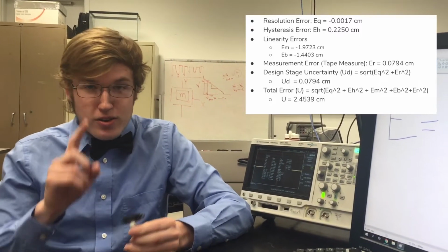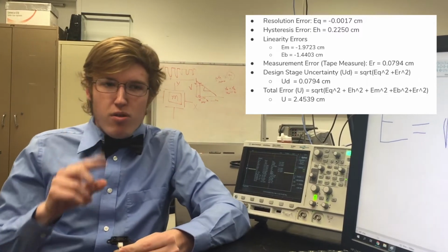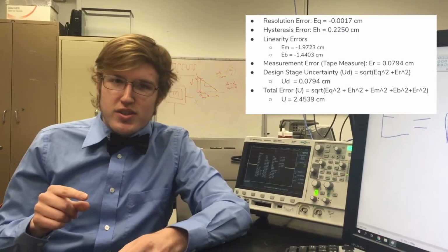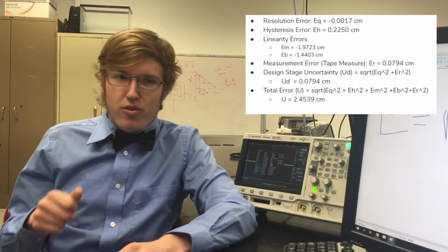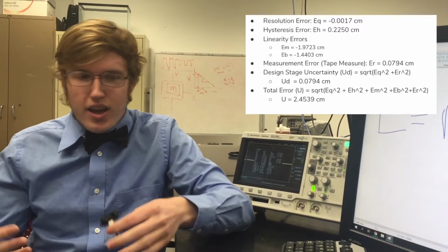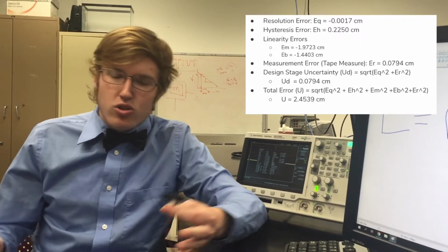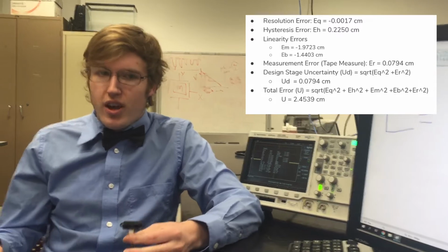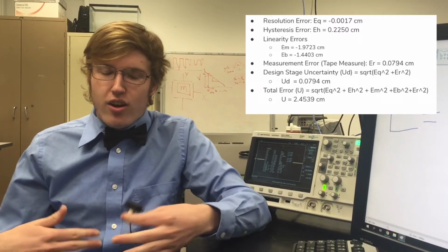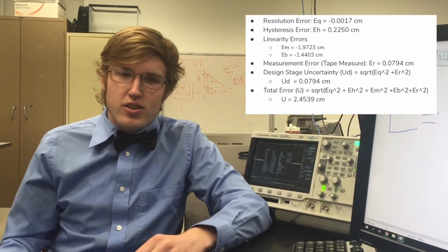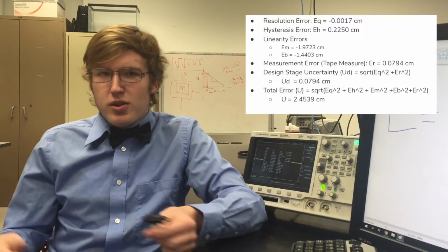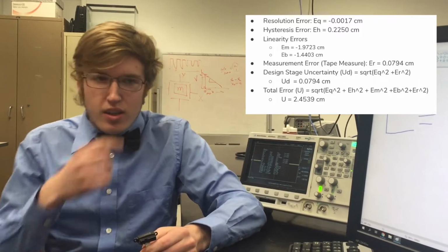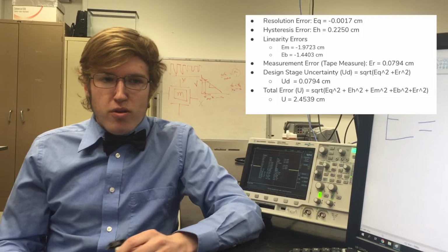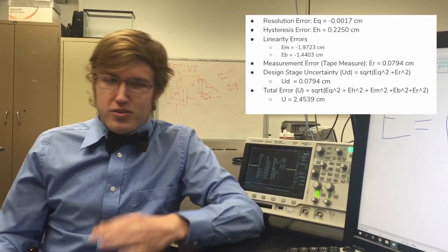Now our linearity errors, those were the biggies. We had negative 1.9723 centimeters and negative 1.4403 centimeters respectively in linearity. Now moving on, our tape measure had an error of about 0.0794 centimeters. When adding all that up together, you get a design stage uncertainty of about 0.0794 centimeters approximately, and a total error of about 2.4539 centimeters approximately.